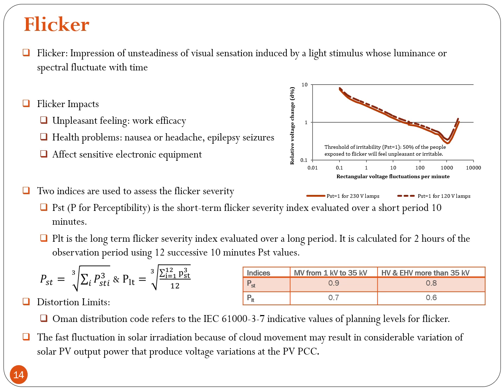Two indices are used to assess the flicker severity. PST is the short-term flicker severity index evaluated over a short period of 10 minutes. And PLT is the long-term flicker severity index evaluated over a long period. It is calculated for a 2-hour observation period using 12 successive 10-minute PST values.